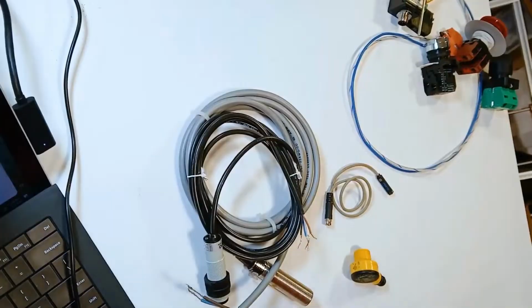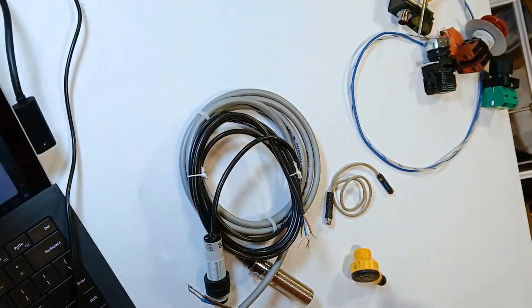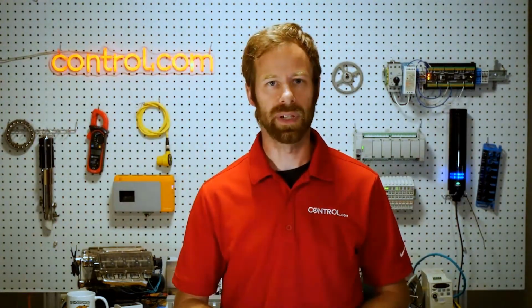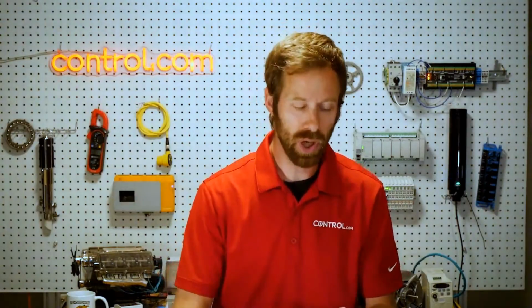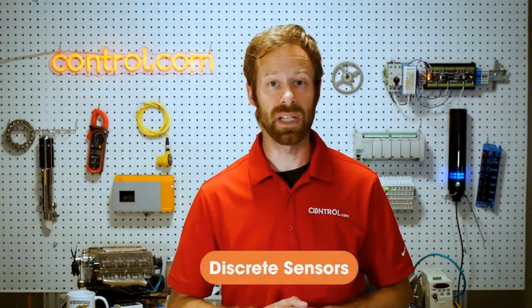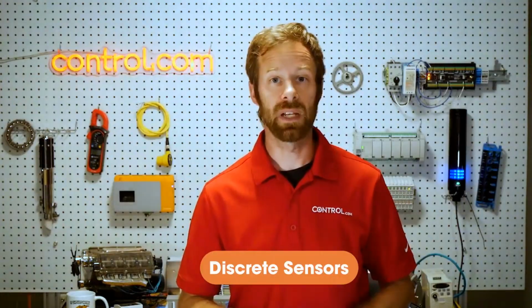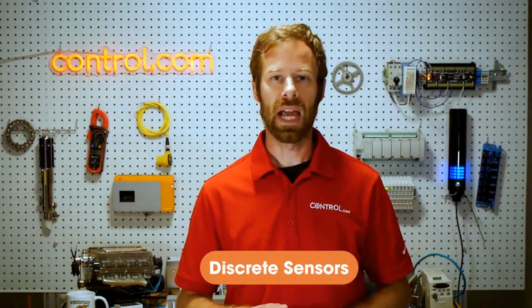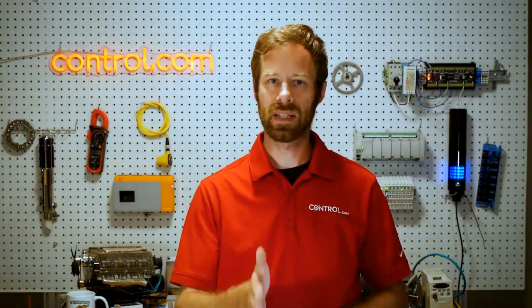We have here a number of sensors, and these sensors have usually either 2, 3, or 4 wires, with 3 being the most common. 3-wire sensors is a really common term to hear in industry for this reason. These provide more than just the simple metal contact on-off action because they can be divided up into a couple of different categories. The first is discrete sensors. Discrete does mean on and off, which means that we have a certain threshold or a set point at which we want that sensor to trigger.